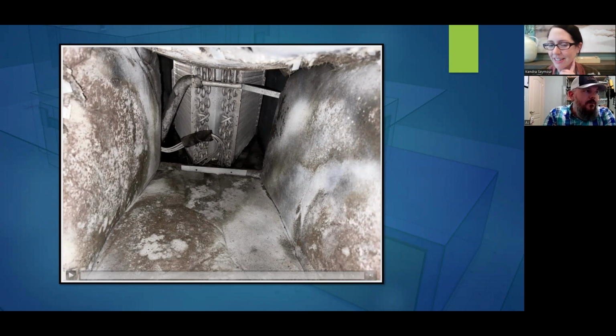So what we're looking at right here is the supply air plenum of a system. This supply air plenum is sheet metal. It's insulated on the inside with a porous fiberglass liner. And as you can see, it was coated at some point with an antimicrobial coating, and it clearly has microbial growth growing on it.